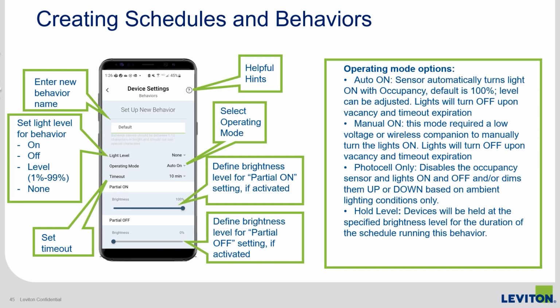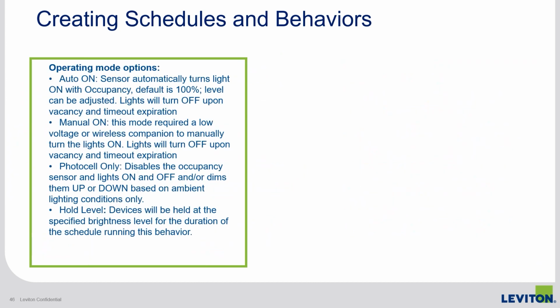Last is none. This means there is no specific lighting level that the lighting will go to when the behavior starts. This is because it will only be based on other factors such as the operating mode, which can be dictated by occupancy or daylighting levels. For any of the behaviors other than when they are set to a particular level, or if the photocell is disabled, you can select Daylight Enabled to include daylighting with the behavior.